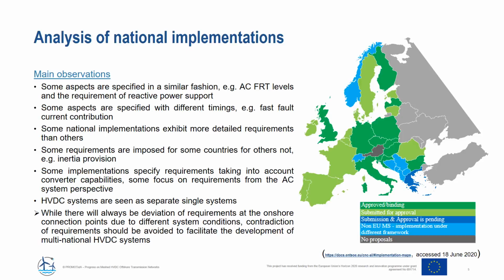Some requirements are only imposed for some countries, for others not at all. So one example here is inertia provision. That could also be related to the number of HVDC connected power plants within those systems. And then some implementations specify the requirements taking into account converter capabilities, and some focus on the requirements from the AC system perspective. So for example, a power reversal is expected within a few milliseconds or seconds, depending on if you talk about what the converter should be able to do or is able to do versus what you would want from the overall system from a system perspective.